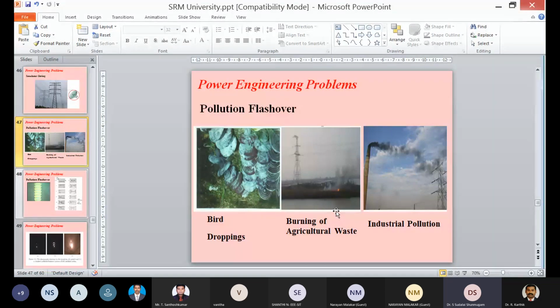The critical problem when it comes to pollution flashover is that this phenomenon cannot be cleared by a circuit breaker alone, unless and until you clear the pollution-causing environment. This phenomenon cannot be overcome otherwise. Because of that, around 2011 or 12, Power Grid gave a steady state recommendation that in India, if we are going to buy insulation, the level of insulation should at least be of medium level. It should be able to withstand medium level pollution. All the insulators in India should withstand that. That is the recommendation given by PGCIL to all the central as well as state utilities.